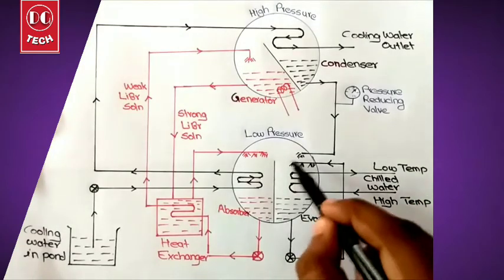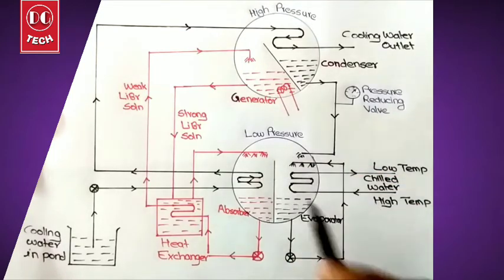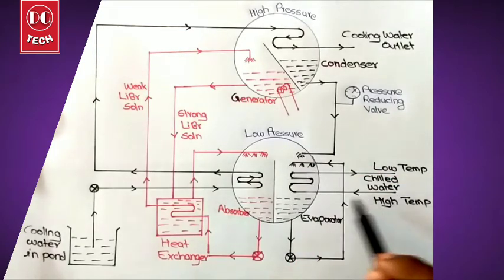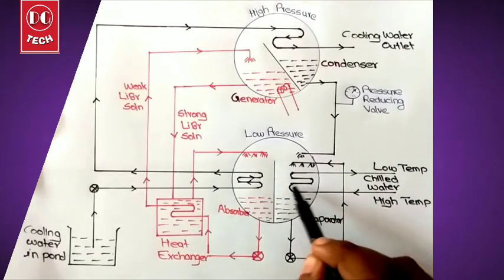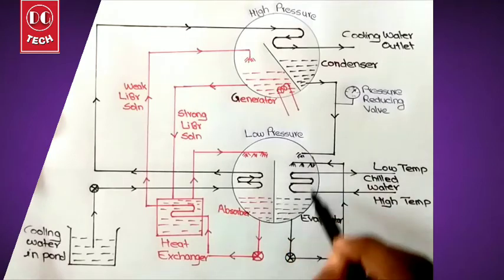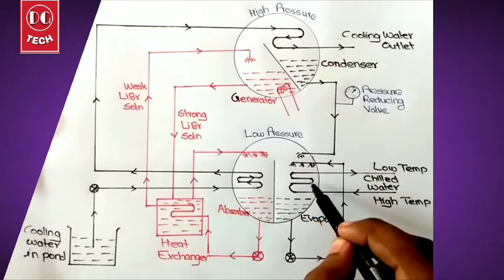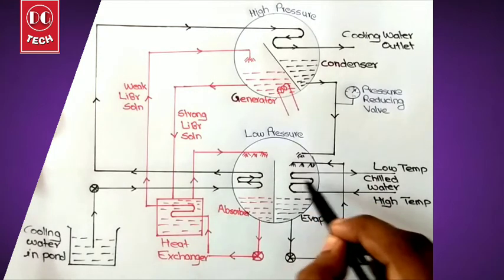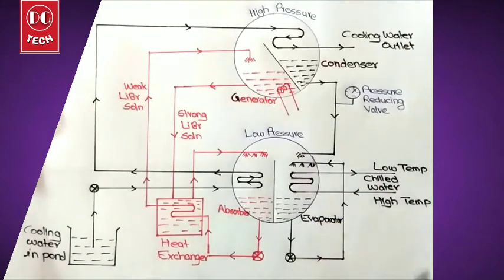Since the pressure and temperature inside the evaporator are both very low, it will absorb heat from the pipe carrying the water to be chilled. When warm water is passed through this pipe, the very low temperature atmosphere of the evaporator absorbs heat from it, so the temperature of the water in the pipe gets reduced and we get chilled water. That is the working principle of the lithium bromide vapor absorption system. Thank you for watching.